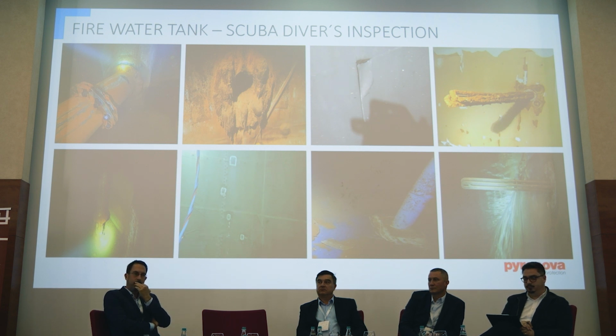So, on the bottom, we can do almost a full revision without the protective coating, also with scuba divers, and we can take the sediments from the bottom so you will not clog your fire pumps. But for the 5 year and 10 year revisions, we are obliged by the standards to empty the tanks and do it the old classical way, and that is the time you actually replace the pipes.